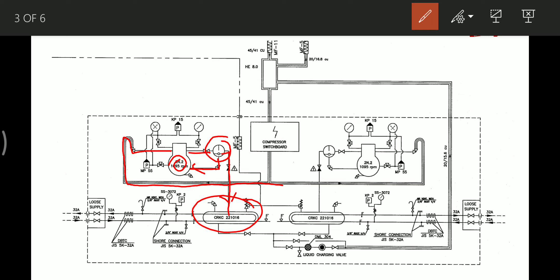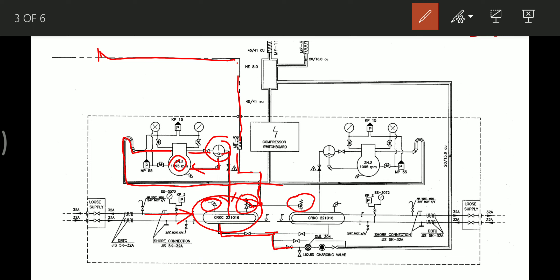This condenser is cooled by fresh water — the central cooling fresh water which is on board ship. The condenser is provided with safety valves, and the safety valves are connected through a pipe to the atmosphere. This is the line connected to the atmosphere and this is a purging cock provided on the condenser. After the refrigerant is cooled in the condenser, it is sent through the filter and dryer.